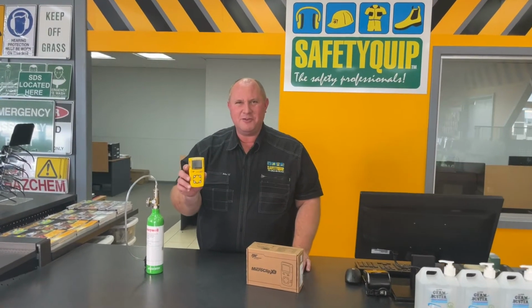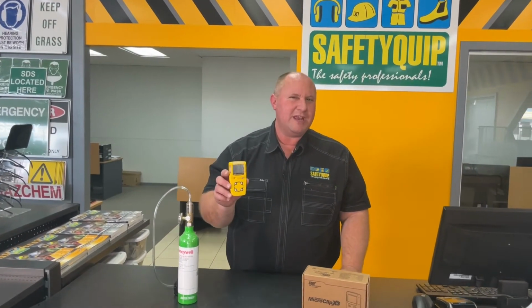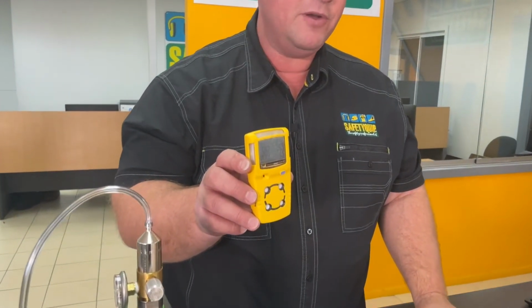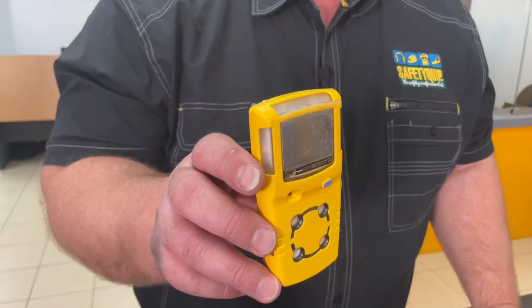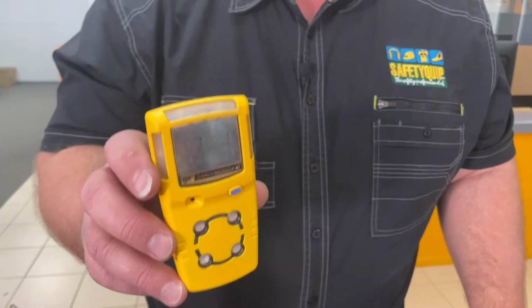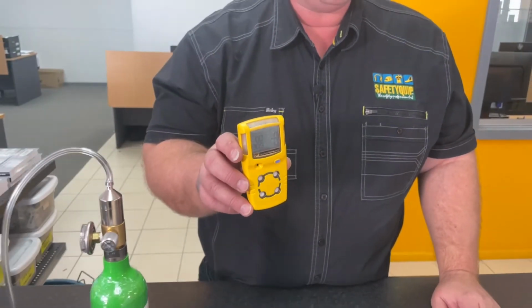The portable gas detector in my hand is the Honeywell BW GasAlert MicroClip X3 gas detector. It's currently the most popular portable gas detector in the SafetyQuip range for confined space entry. One of the advantages of this gas detector is it can be recalibrated manually in the field. So if you're doing remote work and you need to calibrate it yourself out in the field, you can do that if you've got the right equipment and know how to do it.